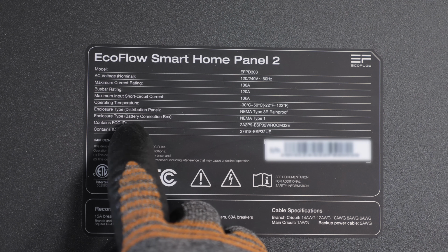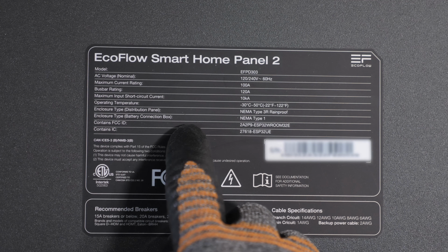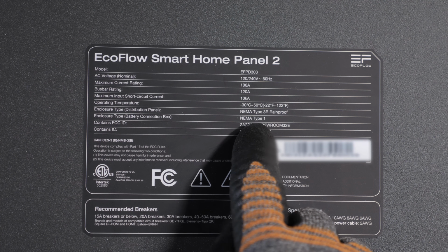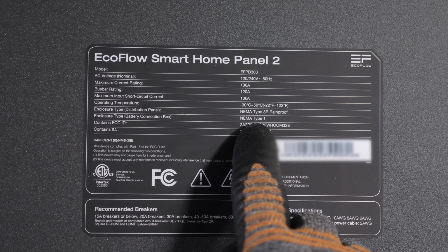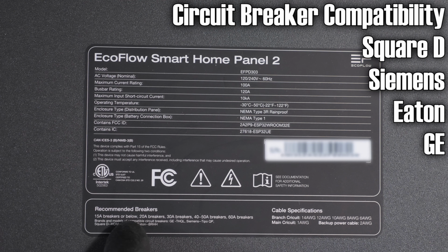The battery connection box attached to the bottom of this panel is only NEMA type 1. It is not waterproof. Recommended breakers right over here: 15, 20, 30, 40, 50, 60 amp breakers. And then it's got your standard cable sizes.